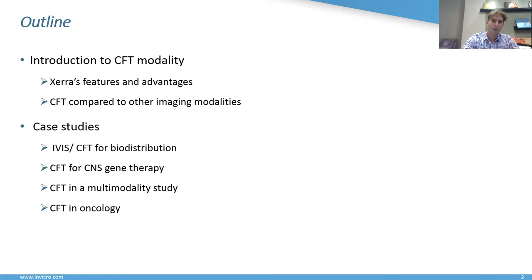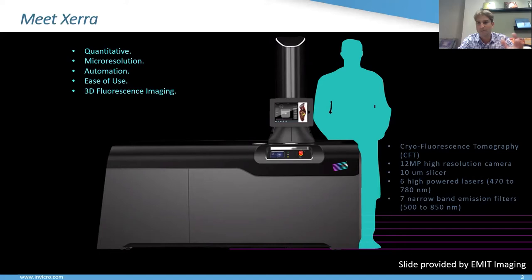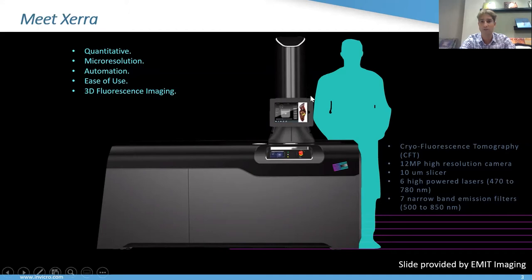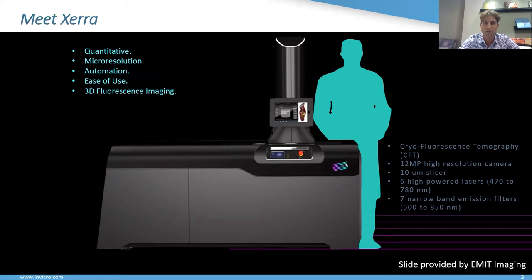So we're all on the same page on what CFT and Xerra are — here are a few slides on Xerra specs. Xerra basically looks like a really sleek cryomacrotome with an optical system placed above in this tower. The block is in the middle, maintained at minus 20 degrees. We have a 12-megapixel high-resolution camera, as well as dedicated lasers and filters, and six channels, which provides great flexibility in selection of fluorophores from visible to NIR.